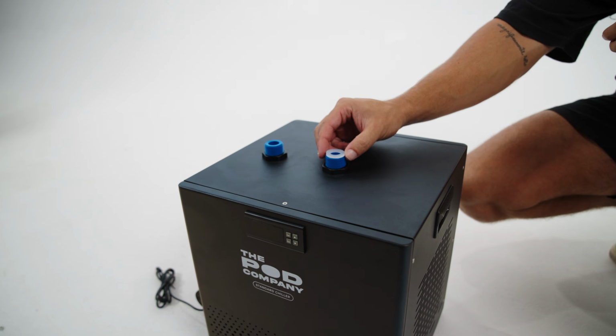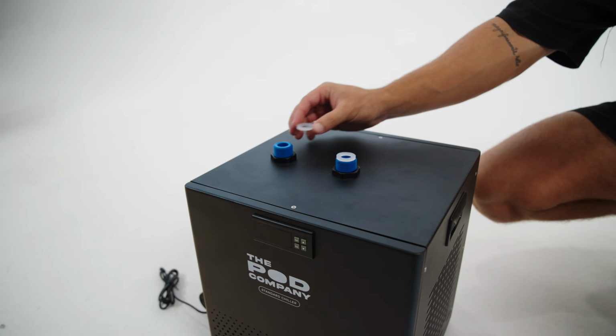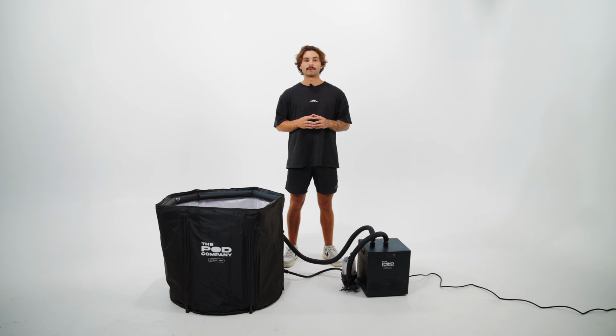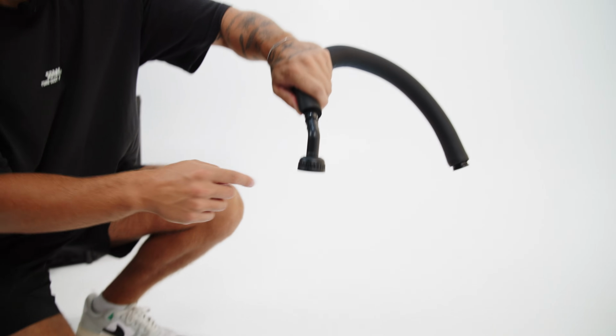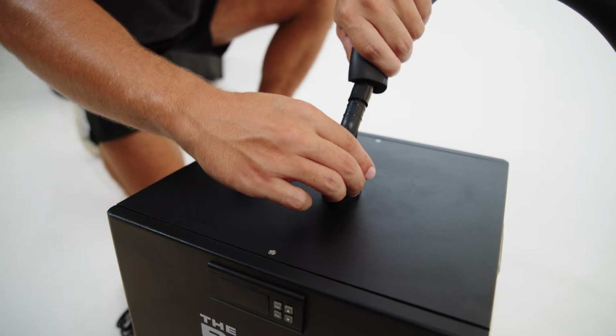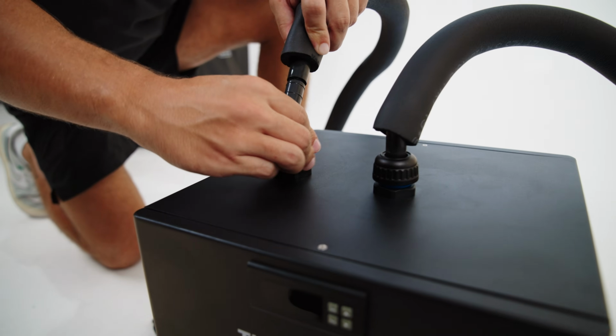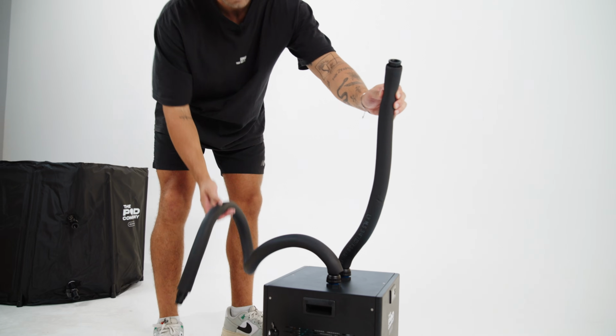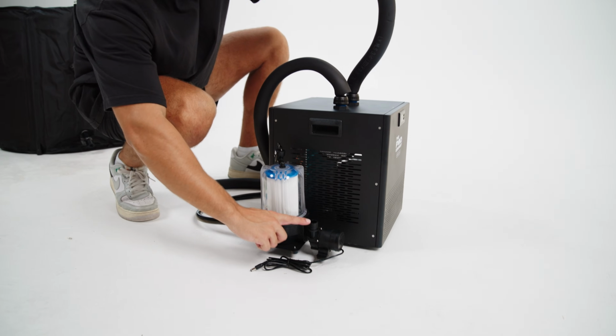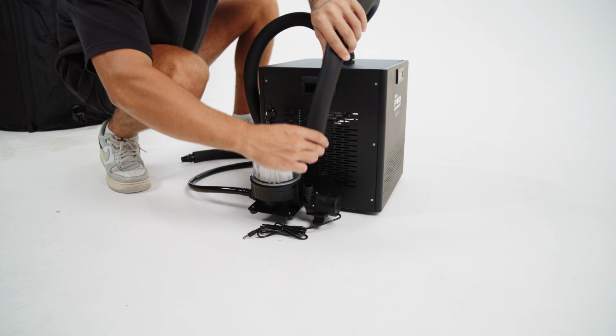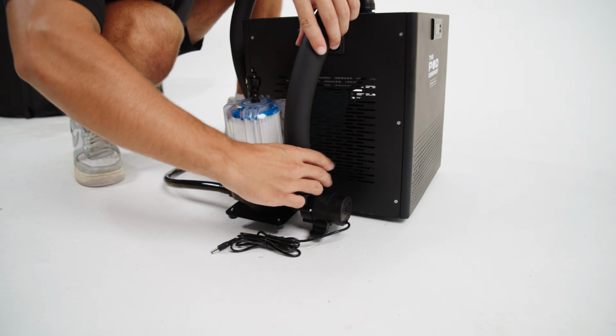Step 3. Place the white rubber rings onto the blue outlets on top of the chiller. These rings are crucial for creating a watertight seal. Step 4. Attach the 2 hoses with L-shaped fittings to the chiller's inlet and outlet points where you just placed the rubber rings. Step 5. Screw the short hose onto the filter unit by connecting it to the remaining threaded port. Ensure it's tight to prevent leaks.